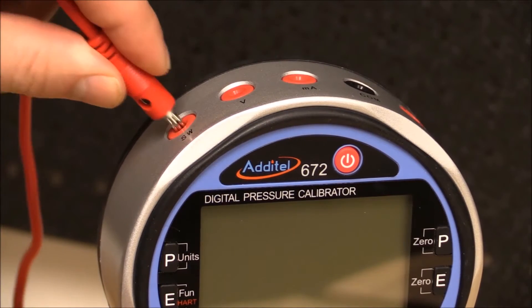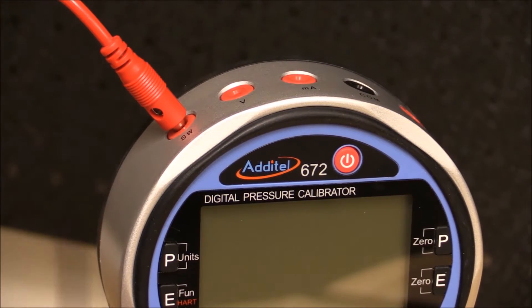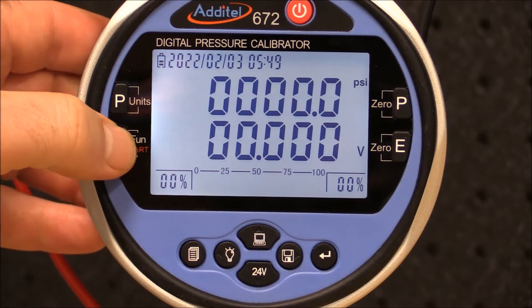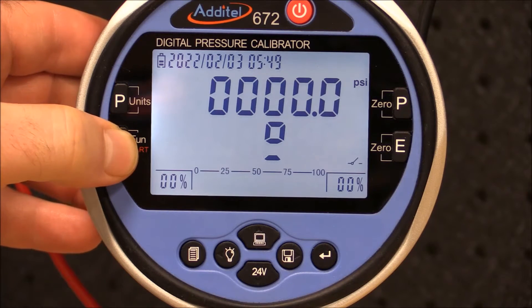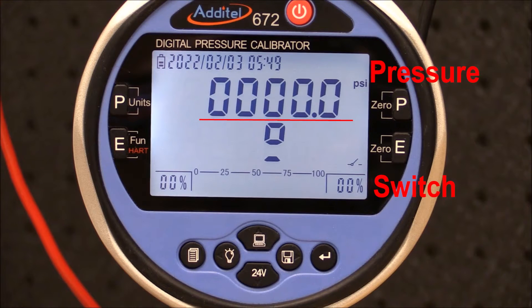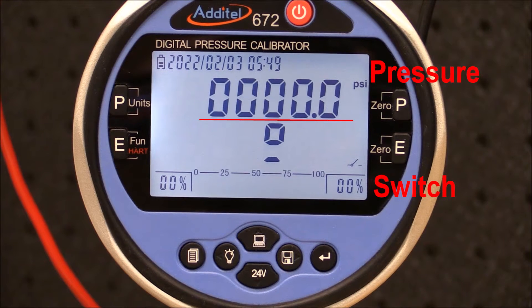The switch terminals can be connected directly to the Additel 672. To set up the Additel 672, simply press the electrical function button until the switch icon displays in the bottom right corner. The dual display now shows pressure and the state of the switch contacts, which are currently open.